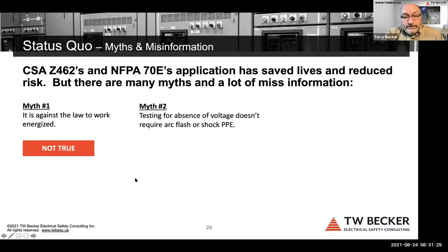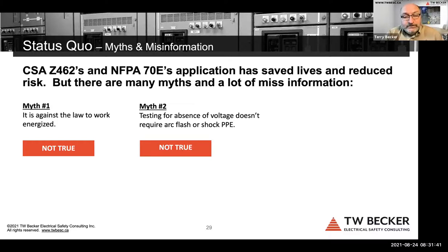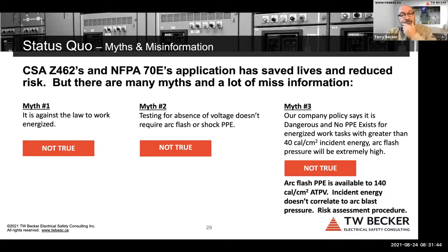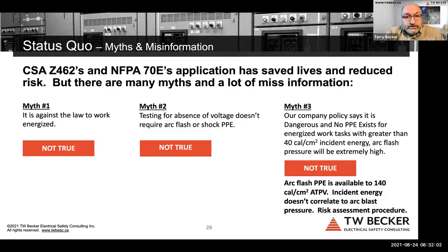Here is a summary of the myths. Myth 1: It's against the law to work energized — not true. Myth 2: Testing for absence of voltage doesn't require arc flash and shock PPE — not true; the qualified electrical worker needs PPE until they establish an electrically safe work condition by proving absence of voltage with an approved test instrument. Myth 3: Our company policy says no PPE exists for energized work tasks greater than 40 cal/cm² and arc flash pressure will be extremely high — not true. Arc flash PPE is available up to 140 cal/cm², and incident energy does not correlate to arc blast pressure.